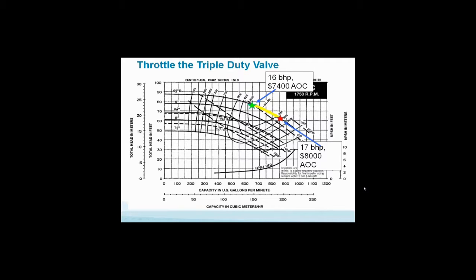We need to trim the pump impellers or put a variable speed drive and slow this thing down. We know we have too much pump head. Why would we run around wasting energy if we don't have to? So let's use our system sizer to see how we might go about trimming this pump impeller to reduce the horsepower required and save some additional money. Remember, we're at 16 brake horsepower. That's where we are right now.